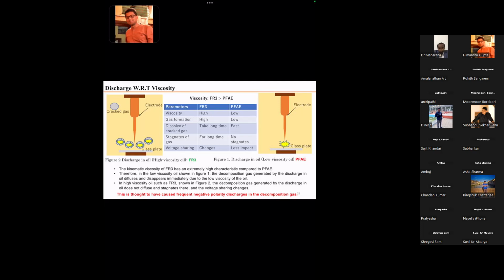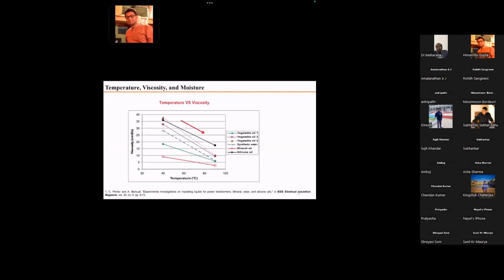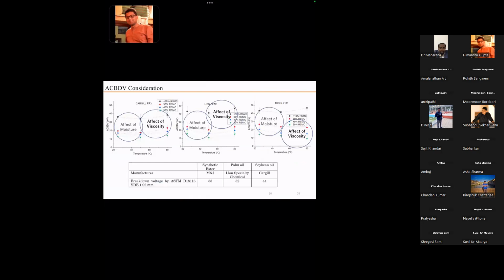In high viscosity oil such as FR3, the decomposition gas generated by the discharge does not diffuse, and combines with each other, changing the voltage sharing - there may be an alteration in voltage. This is thought to cause frequent negative polarity discharge, and gas decomposition alteration is possible, leading to alteration in partial discharge inception voltage. That's why you can find a difference in AC breakdown voltage for PFAE and FR3 - not very high, but significant.